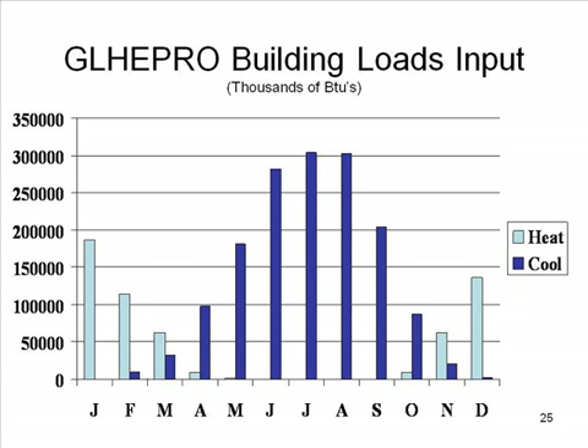That says GLHEPRO up there. That's just one of about 4 or 5 different good commercial design programs. This particular program wants to know what the thermal loads are by month. Other programs want to know the heat pump run hours for a particular zone on a yearly basis. If you're in a commercial business and you're not looking at determining that kind of information, well, your design is not complete. You need to know those because you need to be able to control that.